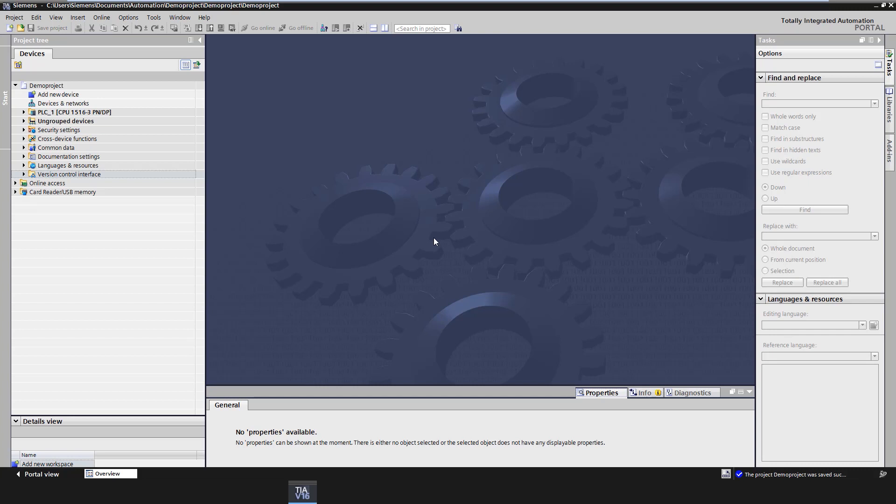The version control interface offers the possibility to export software objects such as program blocks from TIA Portal into a so-called workspace, a Windows directory. VCI is not to be confused with a versioning system like Git or SVN. It offers the possibility to export elements from TIA Portal either in source or XML format.